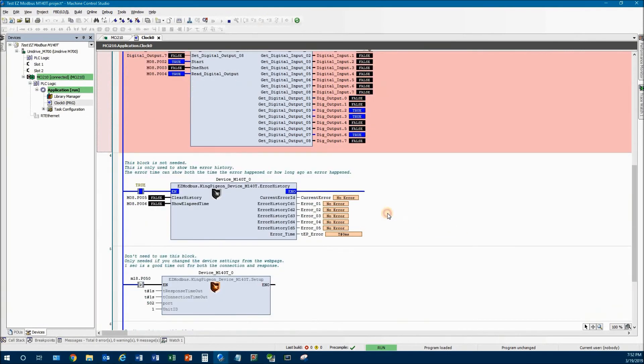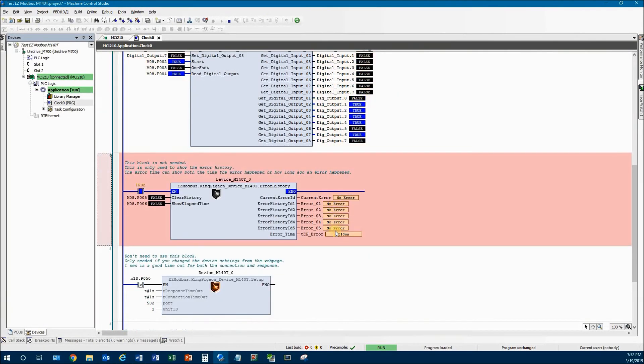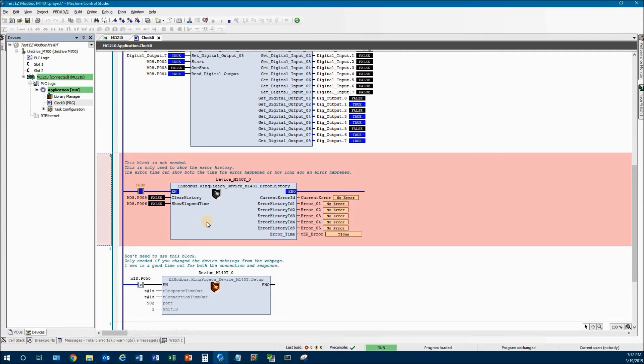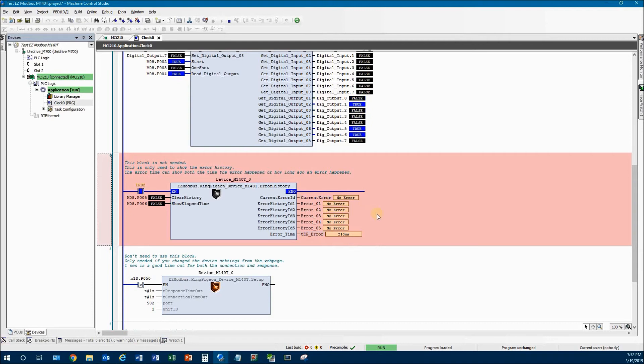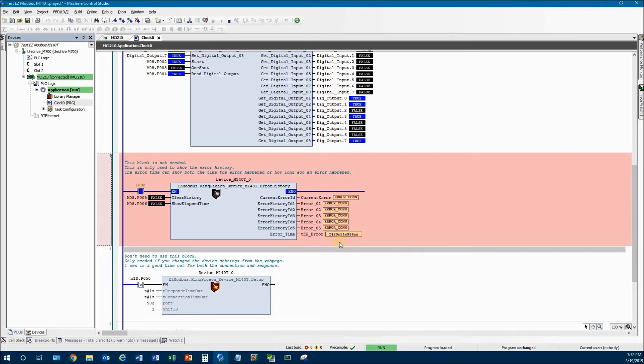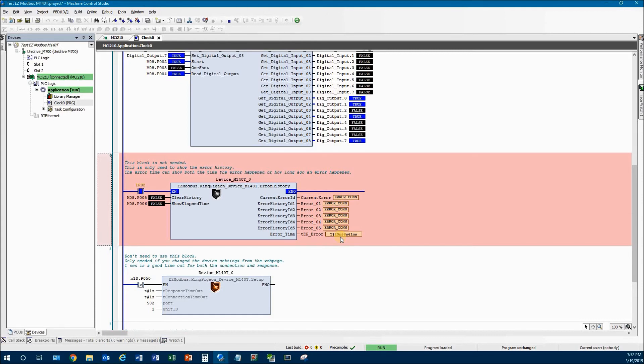So down here, you can see that there's no trip history. If there was history of some sort, you'd see it cycle through here. Okay, so I'm going to actually unplug the bus coupler to show you what I mean. See, now we're getting error connections. And what this timestamp is doing, it's telling you that this is when the last error happened.